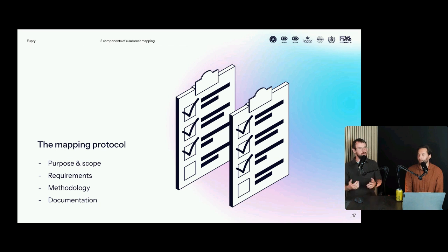What we've seen a few times is to set up loggers, start the mapping exercise, and then wait for hot weather. So you use the historical data to say when it's likely to be in the area when it's hottest. Exactly. And then when you've had a few days of that, your mapping exercise is concluded. As you mentioned before, it's about the critical period in time. You can have some really mild summers, and that will not reflect the actual performance of your warehouse in a very hot summer, for example.